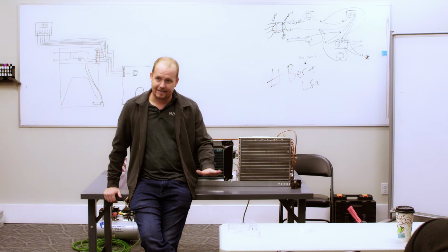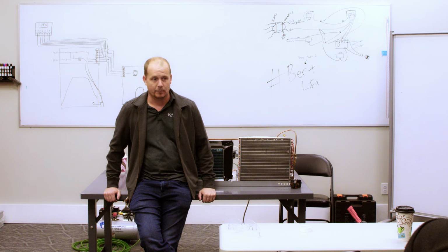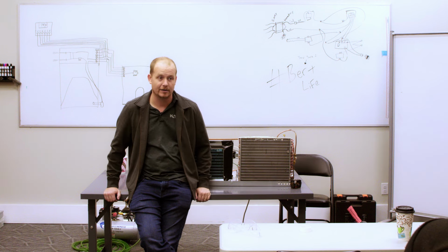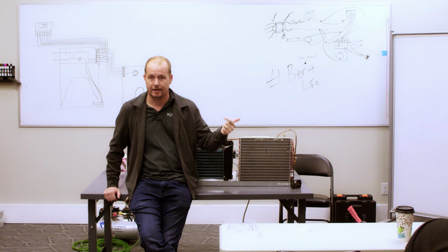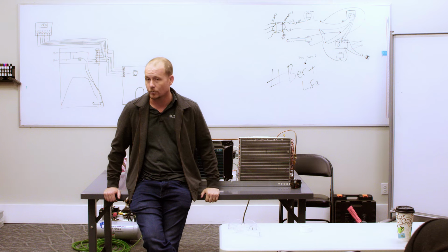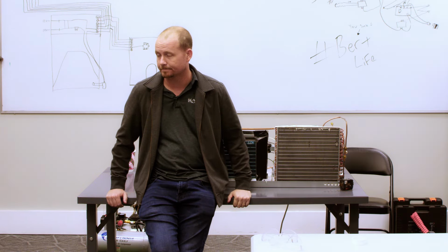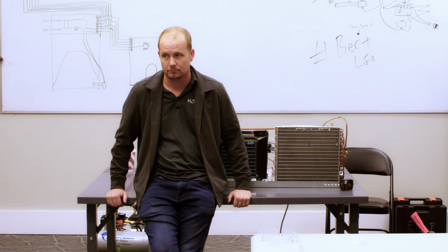So if we have less than that number, say the target is 10, but the differential between our condensing temperature and our actual liquid line temperature is only 3. What do we do? Check coils. Check coils? Okay. Check head pressure. What if it's a brand new system? Check the refrigerant to make sure it's charged right.